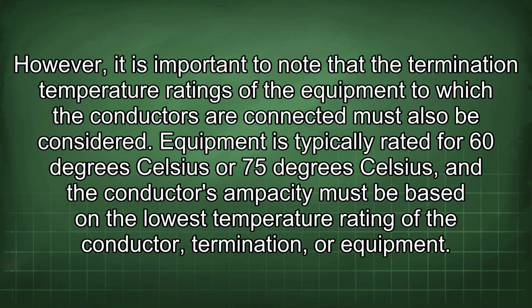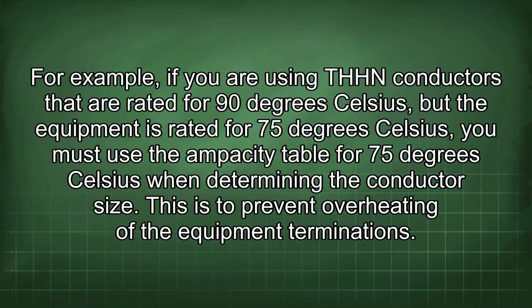However, it is important to note that the termination temperature ratings of the equipment to which the conductors are connected must also be considered. Equipment is typically rated for 60 degrees Celsius or 75 degrees Celsius, and the conductor's ampacity must be based on the lowest temperature rating of the conductor, termination, or equipment. For example, if you are using THHN conductors that are rated for 90 degrees Celsius, but the equipment is rated for 75 degrees Celsius, you must choose the ampacity table for 75 degrees Celsius when determining the conductor size. This is to prevent overheating of the equipment terminations.